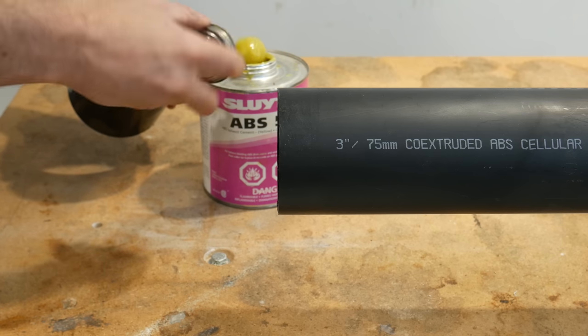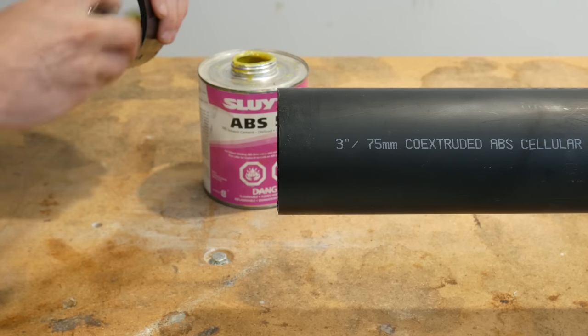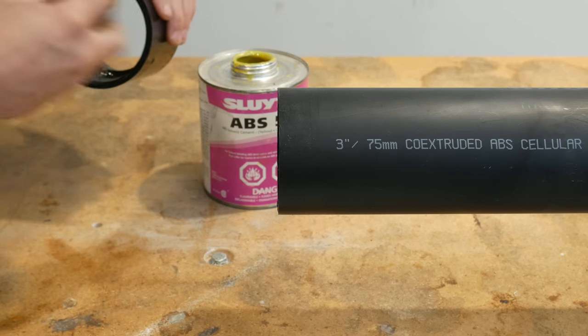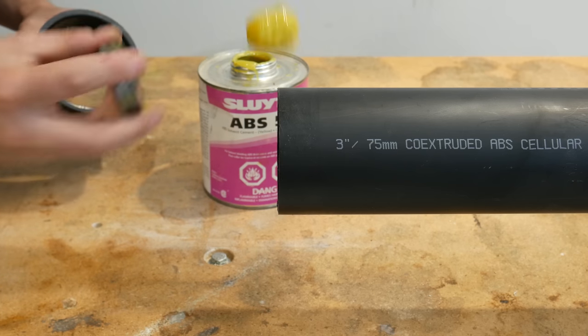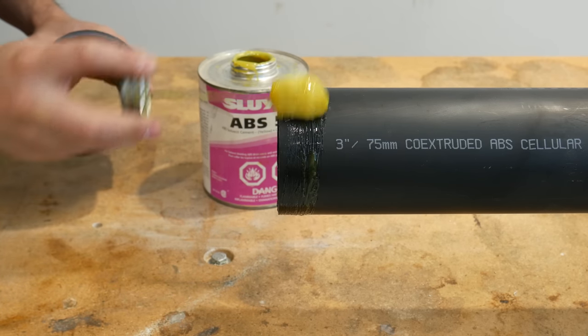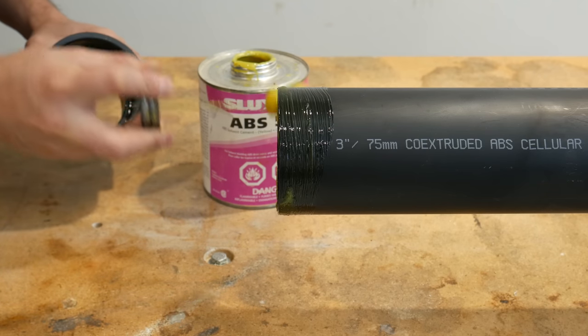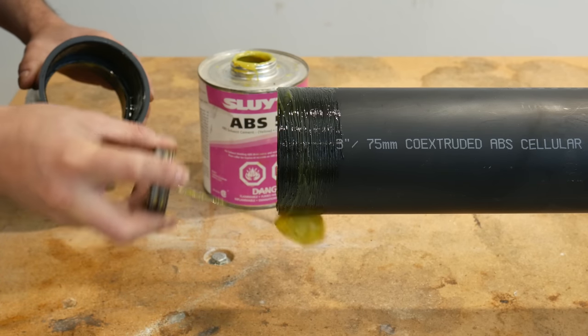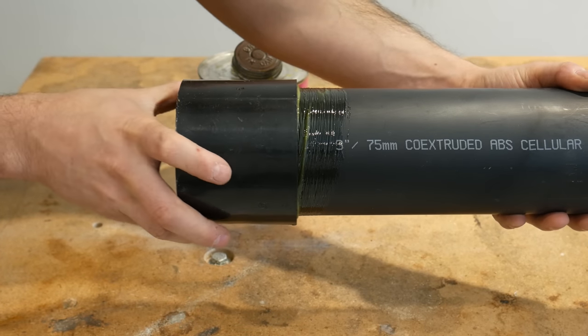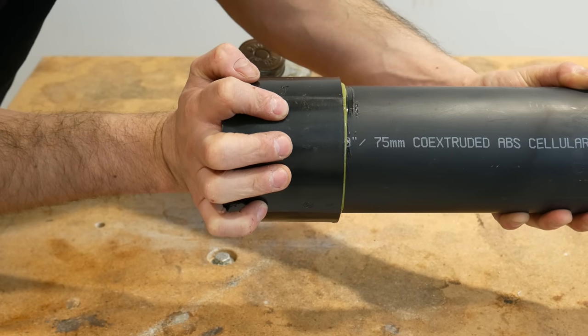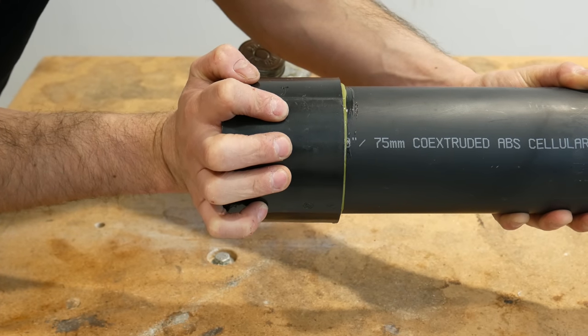Number eight is applying glue to either the fitting or pipe, but not both. The glue or cement acts as a lubricant to ensure full penetration, as simply inserting them dry all the way is pretty tough. On bigger fittings such as three inches and up, it's important to cover both the pipe and fitting hub thoroughly as to not get any dry spots.